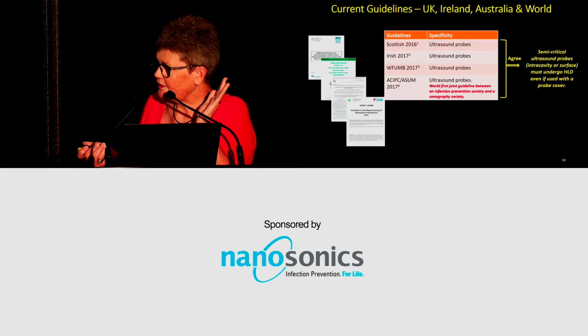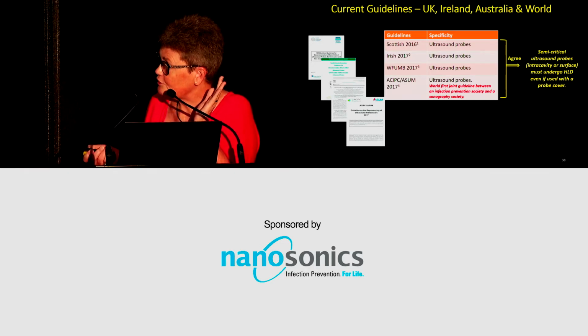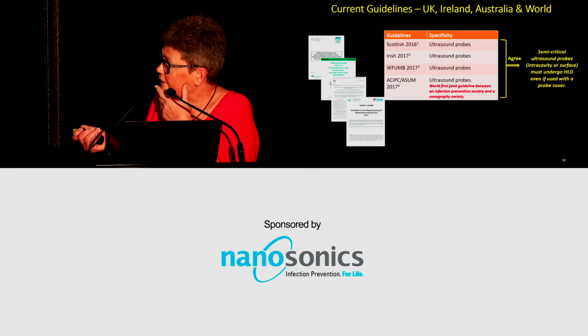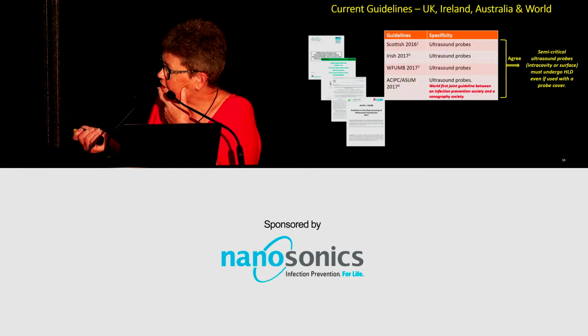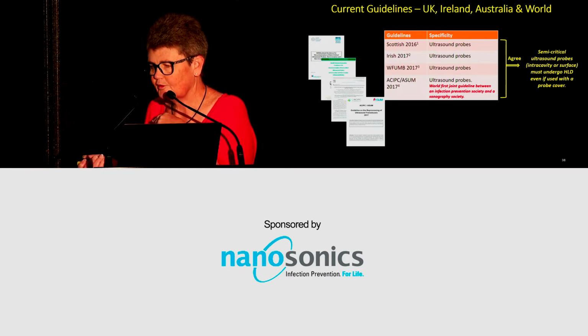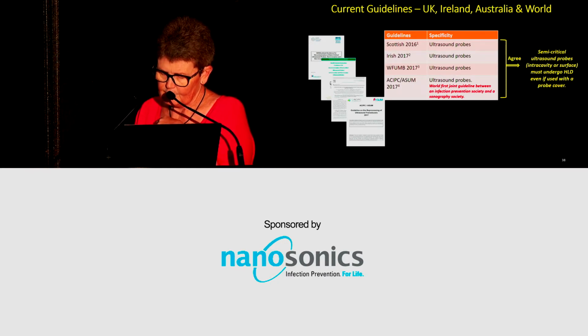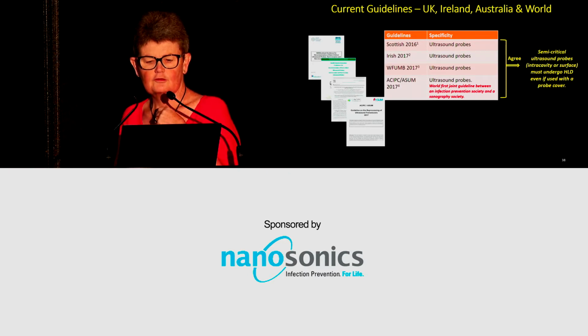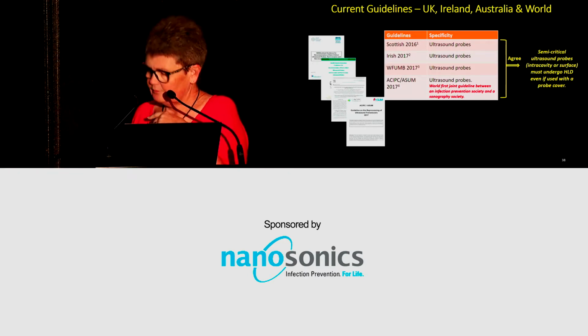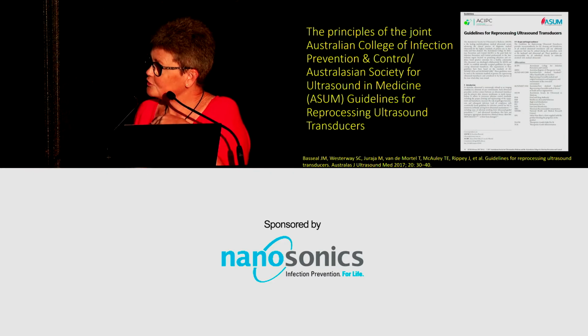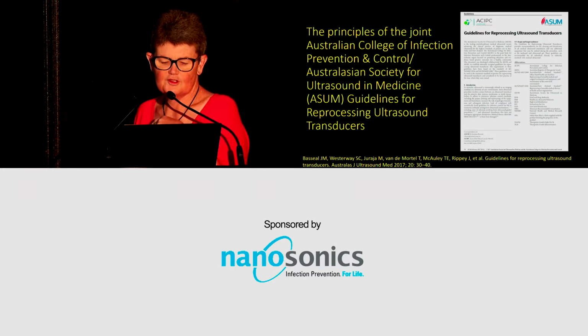The Scottish have been proactive, the Irish have been proactive, the Aussies have been proactive, and so too has this other group around ultrasound probes, and they all agree that probes are semi-critical. Ultrasound probes, intracavity or surface, must undergo at least high-level disinfection, even if the probe is used with a probe cover. So follow the guidance, look for it. I've spoken about the Australian document a number of times this morning.